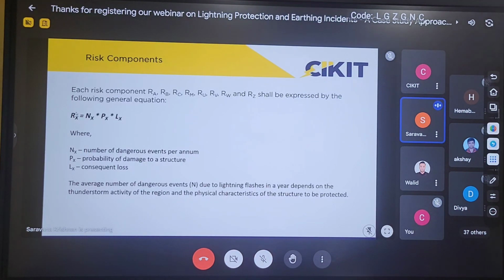what are all the preventive measures that we can take for reducing the risk due to lightning. For example, if there is no lightning protection system installed on my structure and lightning strikes, it will strike my building and result in some losses. If I install a lightning protection system with an air terminal, down conductor and everything, then if lightning strikes, it will be intercepted by the air terminal and the risk is reduced. So the preventive measures include installing the air termination system, installing surge protection devices, and providing warning notices and so on.